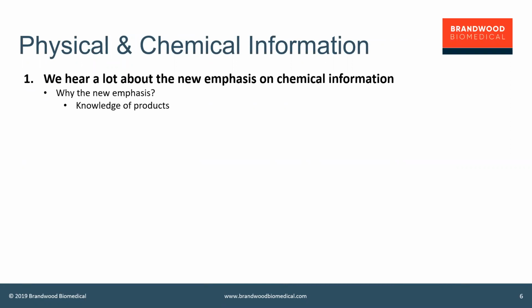Now, you might note here that I've used a word that's not usually used in terms of biocompatibility, and that is products. So really, it's a thought about what is placed onto the market and how much is known about it. Perhaps to our detriment, the medical device community does not actually have a very great knowledge of what their products contain or are constructed from.